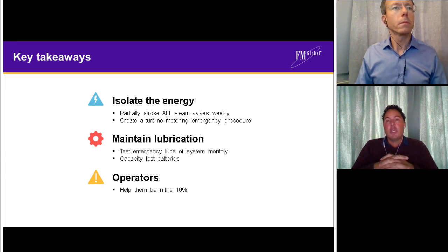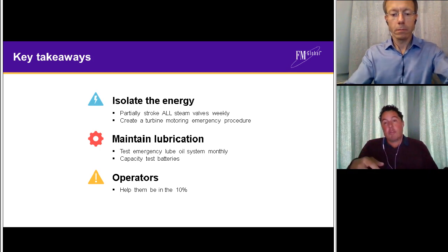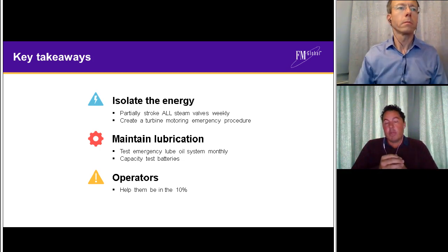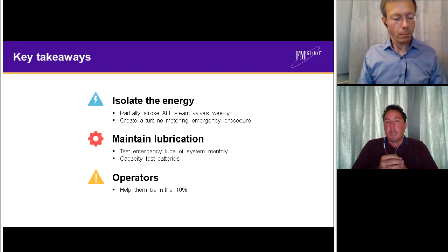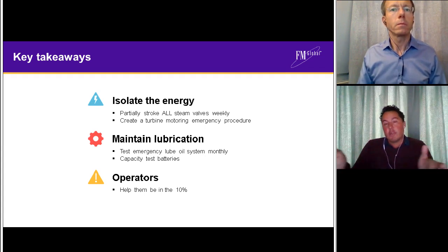but it's also got an incredibly long life. So if you look at waste to energy, for instance, which is a growth industry in this country and where we're seeing a lot of new steam turbines installed, the initial design life of those plants is sort of 20, 30 years, but they've got batteries being installed that need to be replaced every 5 years, 10 years if you're stretching it. But I would argue that you probably don't want to be stretching the battery life on your turbines. Whereas if you install NiCad batteries, you have one set of batteries for anywhere between 15 and 20 years. So the lifetime cost of that battery installation is comparable, if not better, than the valve regulated ones, but it needs to be spec'd at the outset. So on the whole, a good news story, but we've still got some room to improve, I think.